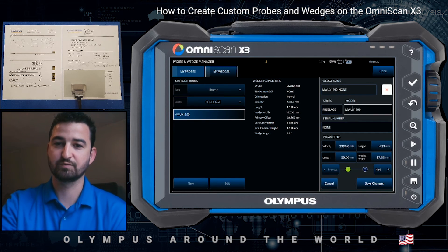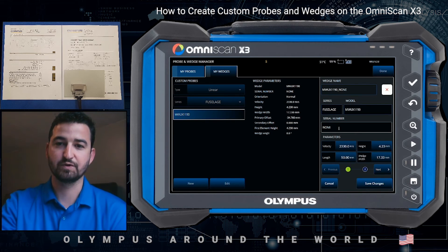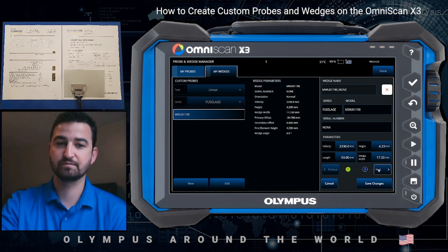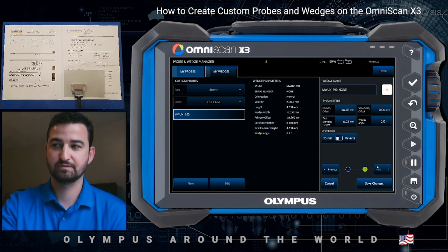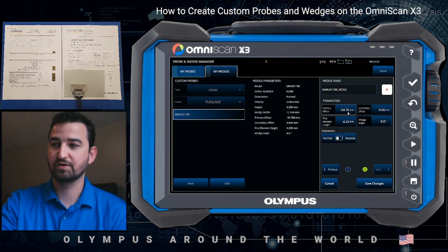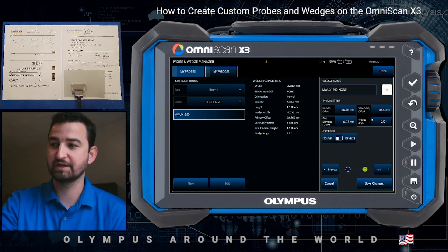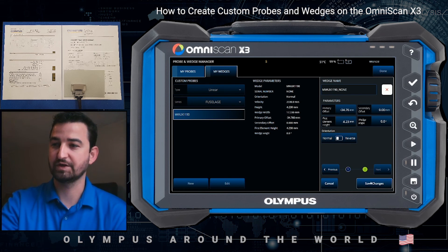We entered fuselage as the series to identify and sort. The model number was provided. Some wedges are serialized, but this one is not, so we put none. We enter the velocity, the height, the length, and the wedge width. We hit next. We enter the primary offset and the first element. This is a lateral wedge, so we didn't enter a secondary offset or wedge angle. We hit save.